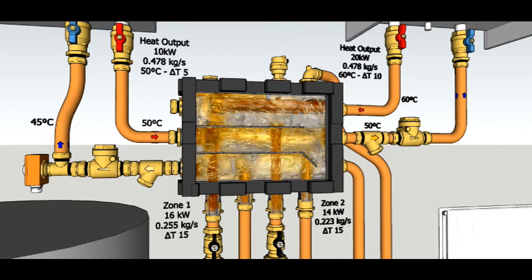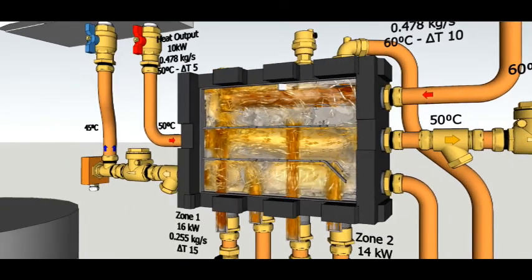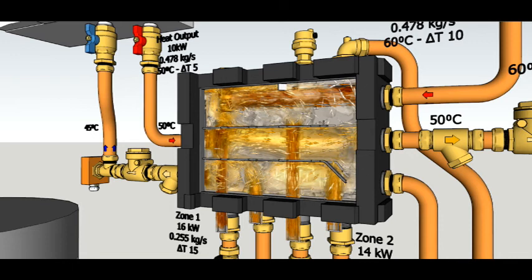Even though it's mathematically complex to think about, the logic of the whole thing is so simple. This particular viewing angle gives us a very clear view - you can see all of the water coming from the left in the middle chamber has been taken entirely into the gas boiler, and then the gas boiler simply carries that water on and heats it to its full design temperature. This really highlights the difference between energy zone and any other form of manifold or pipe configuration on the market, including low-loss headers or close couple T's. The fact that you can put the appliances together to do exactly what they're designed to do and make them work in harmony with each other offers a very easy way to do top-class work. Any reasonable plumber can make a very neat job by simply putting the manifold on the wall and connecting it up properly - the logic is already done.